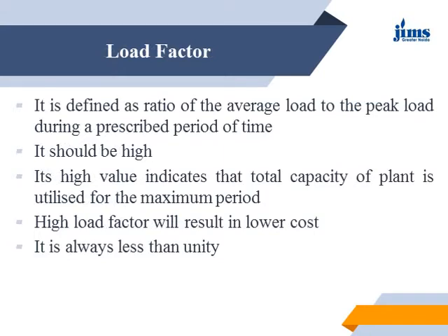So load factor is defined as the ratio of the average load to the peak load during a certain prescribed period of time. Means that it is the ratio of the average load to the peak load. So average load will always be less than the peak load, and if it is the ratio of the average load to the peak load, this should always be less than 1. So this ratio, that is load factor, is always less than 1.